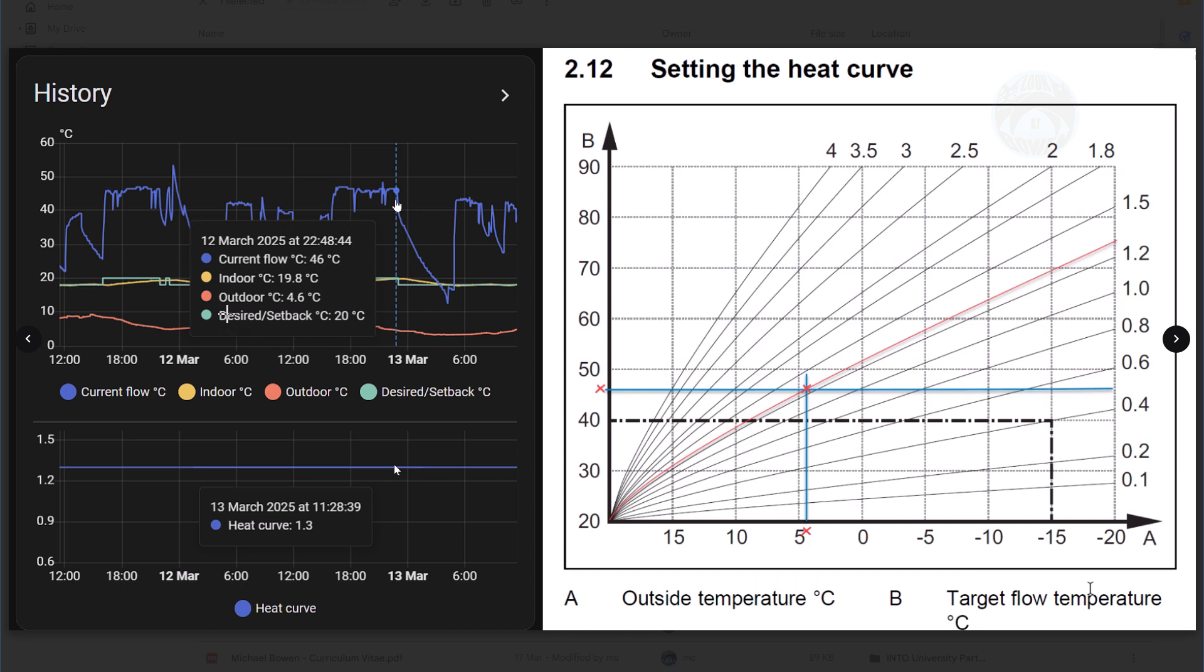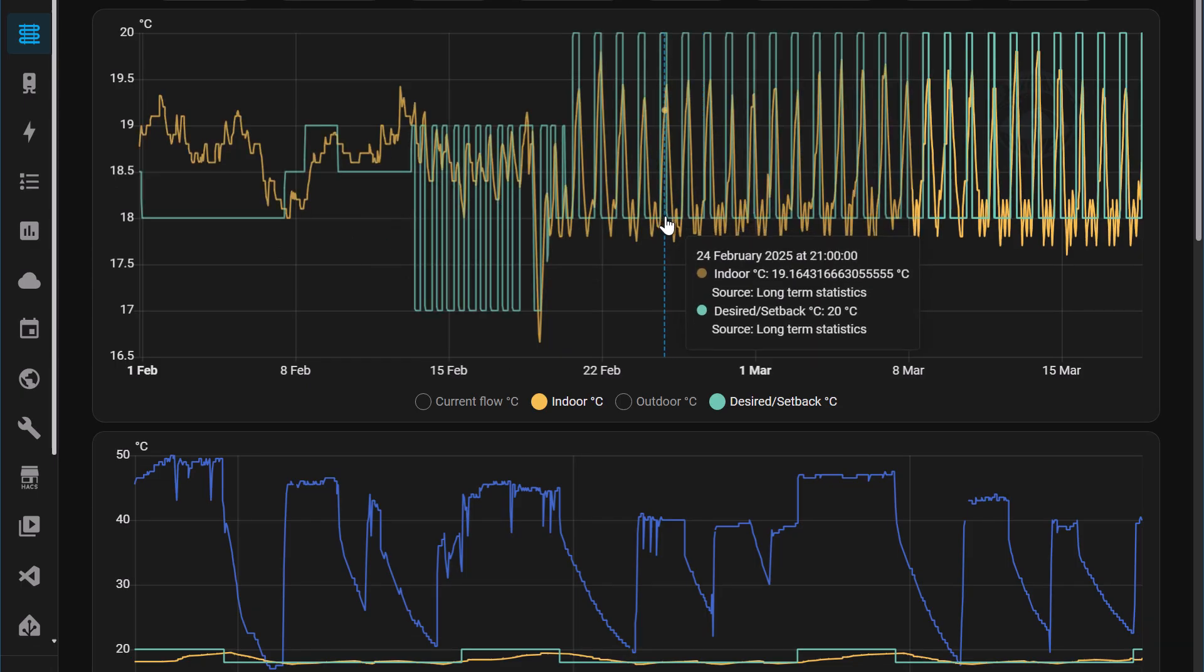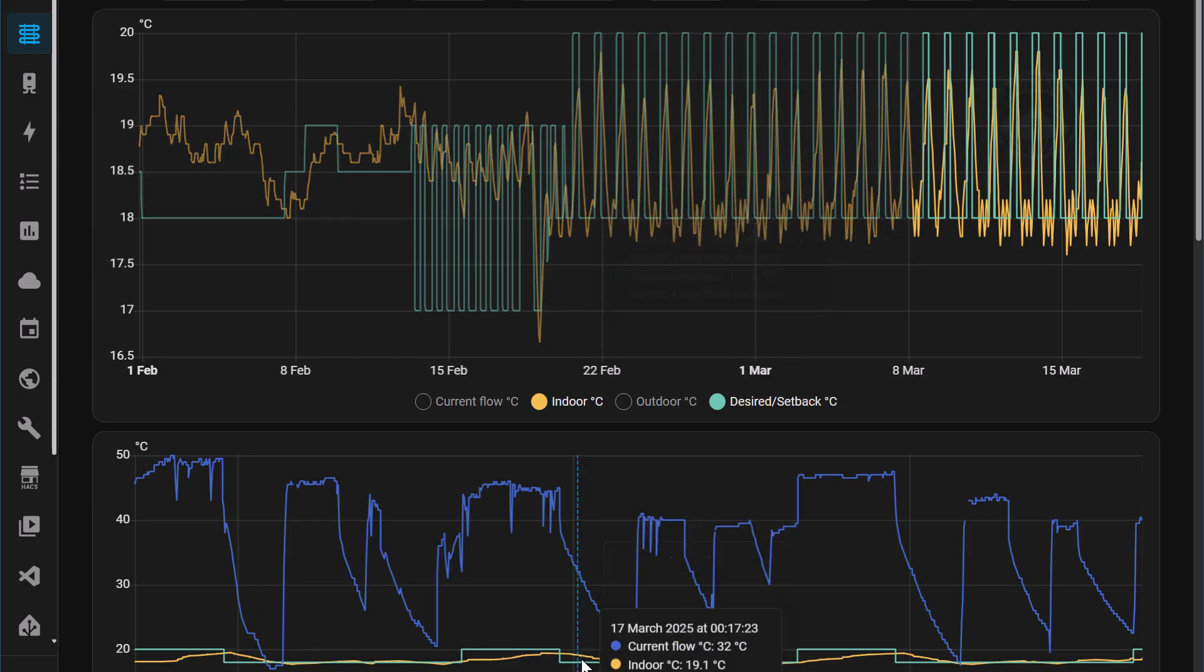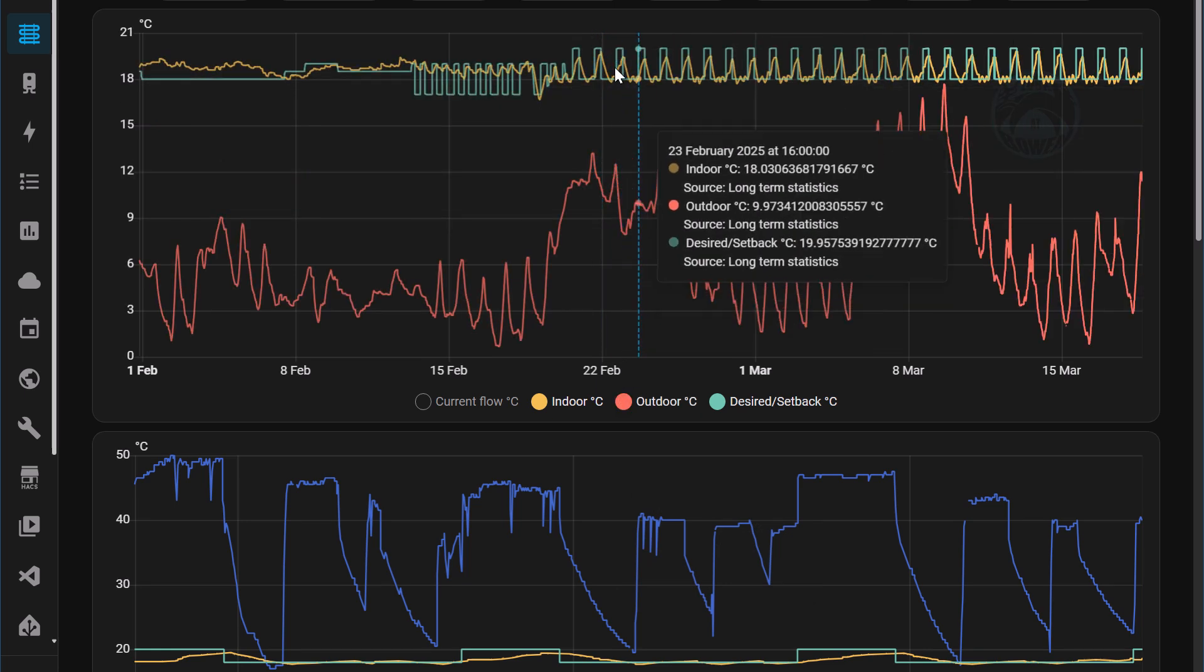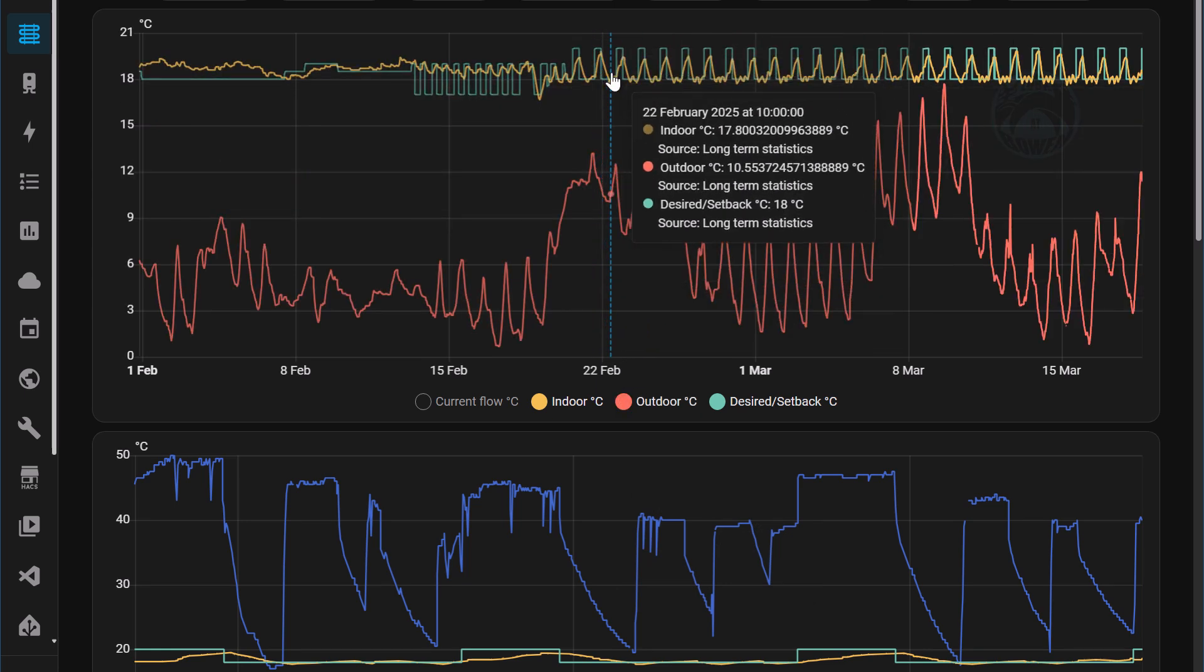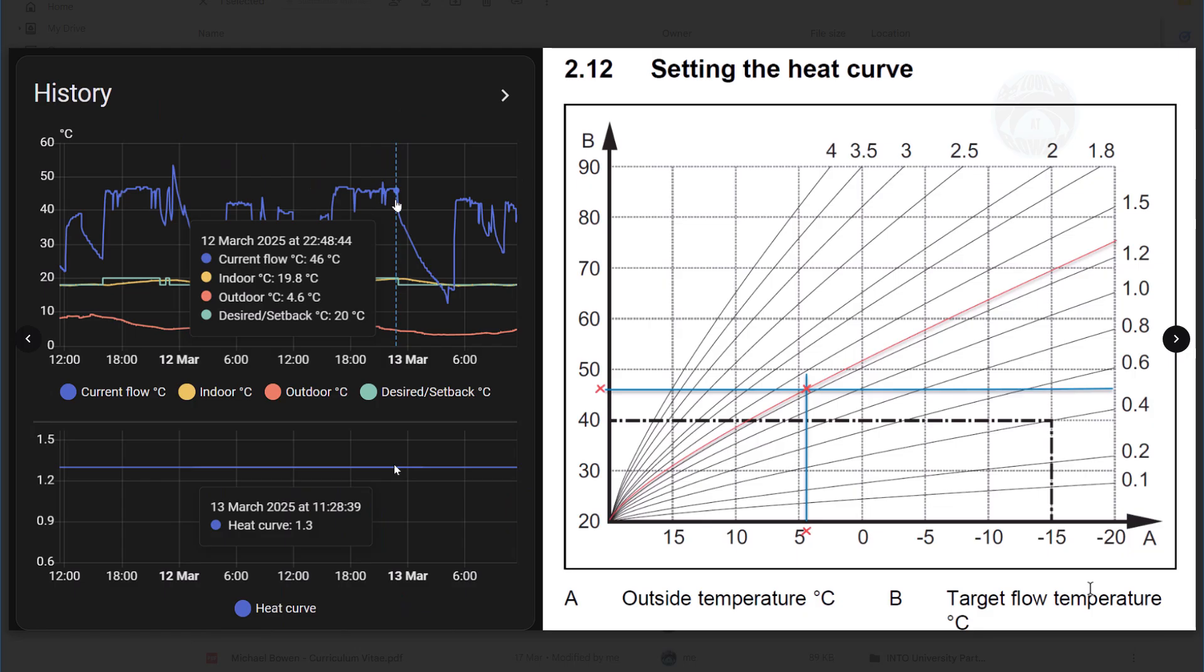So what I've done is I've drawn a blue line from 46 degrees across the page. And then the outdoor temperature is 4.6. So remember I said when using expanded, it uses the outdoor temperature as well as the indoor temperature from the thermostat, the sensor comfort thermostat. And it also uses the heat curve. So that's why having the right heat curve is super important. I've got the outdoor temperature of 4.6. I've put it on there as around about at that point. And then I've gone up to the top.